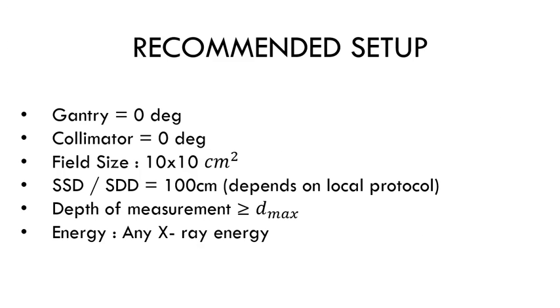Depth of measurement should at least be D max. It can be more than that, again depends on the local protocol. This test can be done for any X-ray beam energy. Let's go through the step-by-step procedure.